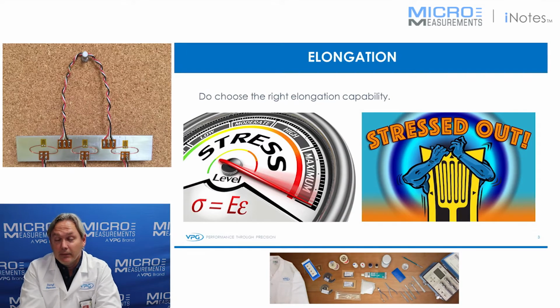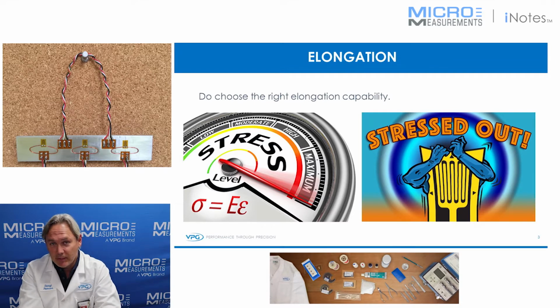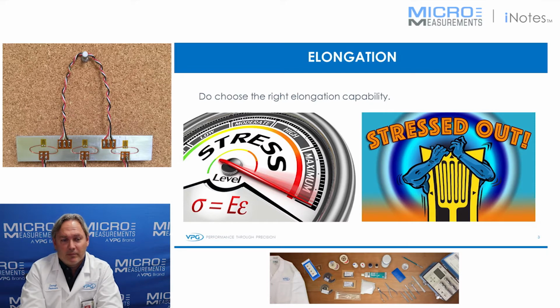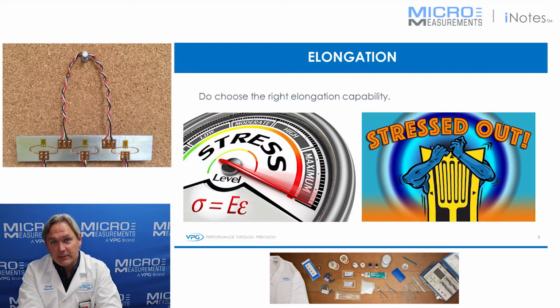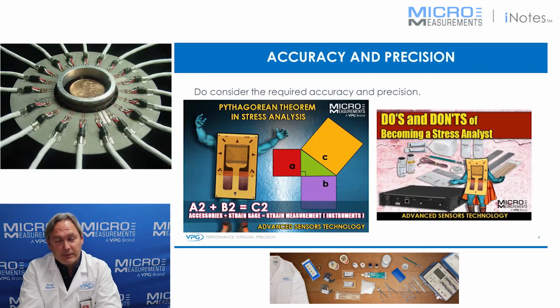Do choose the right elongation capability. You'll find strain gauges have a variety of different elongation capabilities based off of what they're made from. Cast polyimide and laminate polyimides typically have a higher elongation capability, where some of the reinforced laminate materials that are an epoxy or epoxy phenolic based typically are capable of a lower elongation, and we're here to help you select the right one.